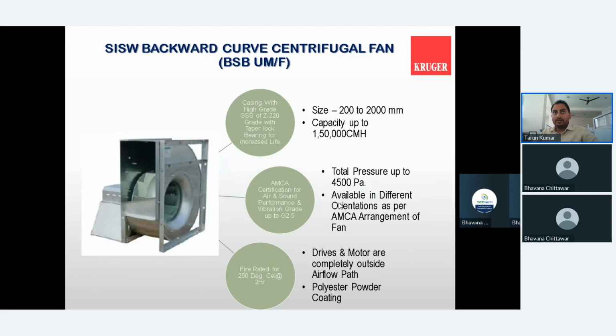So mainly the SISW fan, which is very famous for kitchen ventilation, is available with the belt driven as well as the direct driven arrangement. The main key feature of the kitchen SISW fan, and what we have to think before proceeding with kitchen ventilation, is that we have to safeguard our motor, because as everyone is aware, oily and greasy particles will always be in the airflow path, as well as your air temperature will always be more than 60 to 80 degrees.